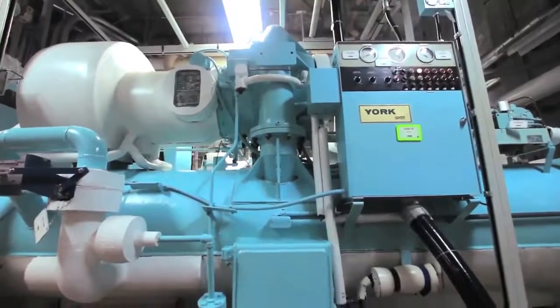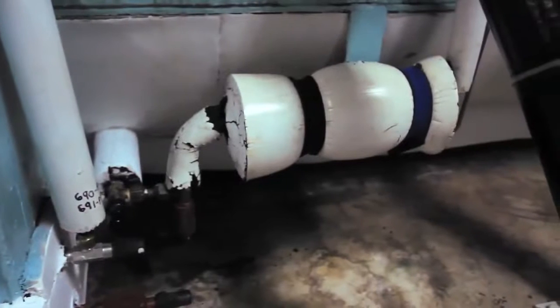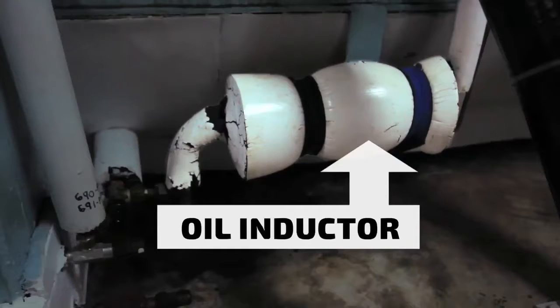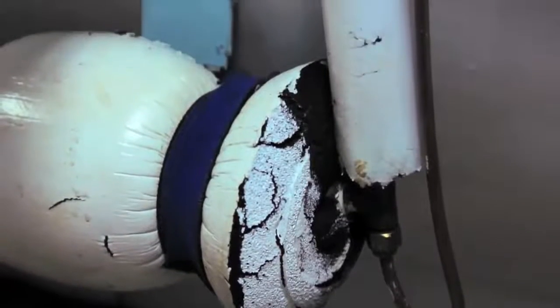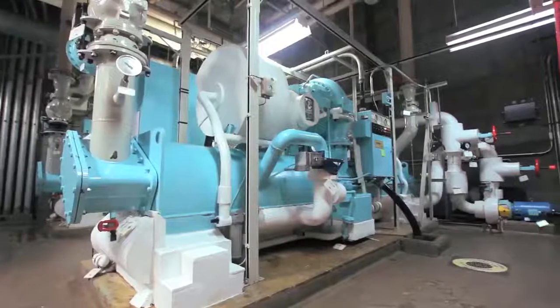There's one last system to discuss. The oil eductor on this unit is in continuous operation. It removes oil from the extreme lower levels of the shell and returns it to the crankcase. There is also a filter in this system which removes particulate and moisture.